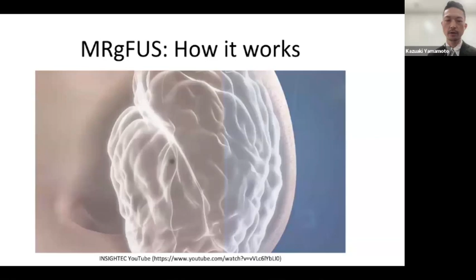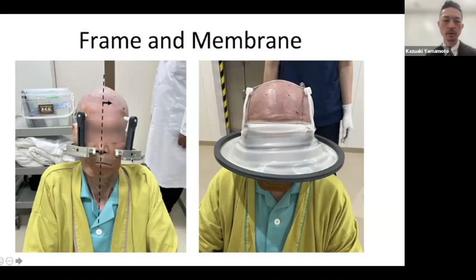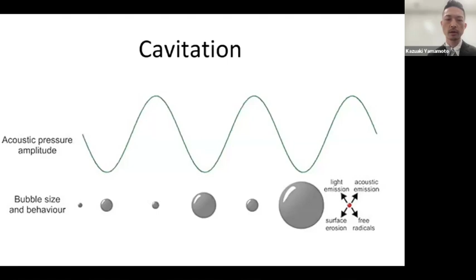For treatment, the head must be completely shaved to avoid cavitation caused by air bubbles. A silicone membrane is applied above the frame like this, which is a CRW frame with MRI-compatible carbon posts. Cavitation is a phenomenon where ultrasound compresses and releases air bubbles, potentially causing tissue damage. This is why shaving and degassed water circulation are essential.